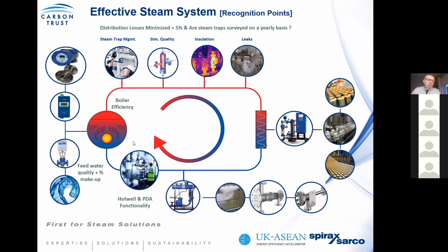Why? The purpose of the boiler is to generate high quality steam and export it to end users. However, the quality of steam at the end users is not that which is generated by the boiler, and steam, by its very nature, will want to give up its energy to its surroundings, in doing so condensing. And as we know, water is an excellent insulator. So if you allow a system to condense steam, you can reduce the heat transfer efficiency of the end using plant. We will then look at the heat transfer efficiencies of those users and what can be done to optimize them.